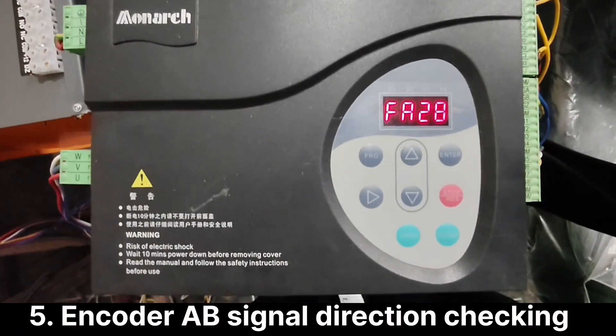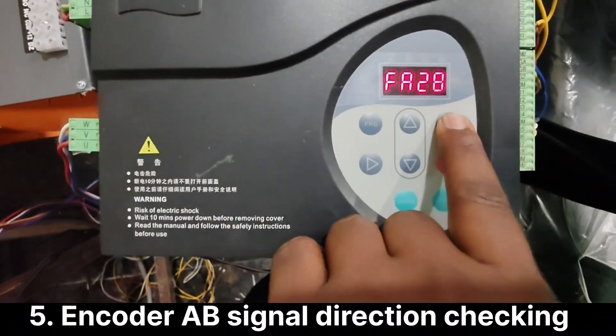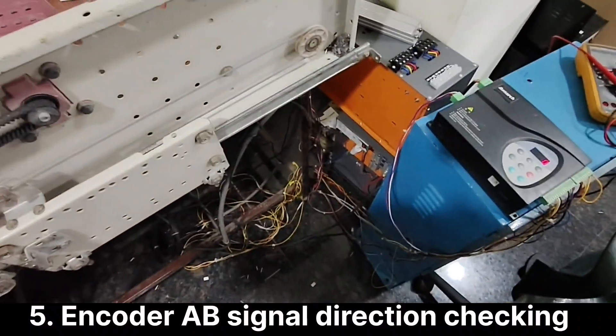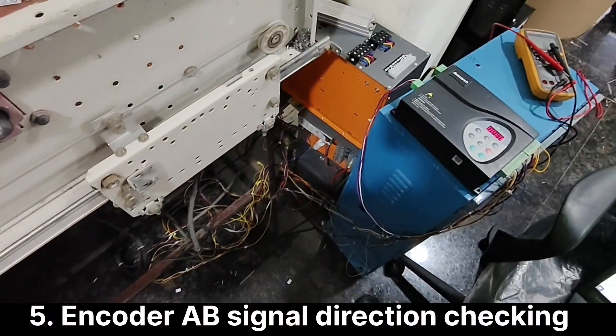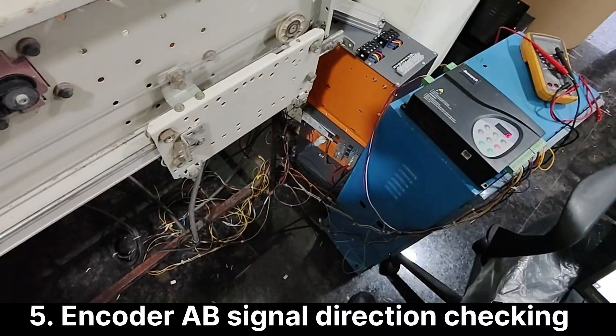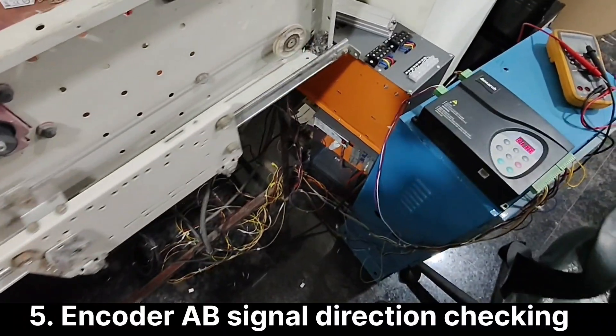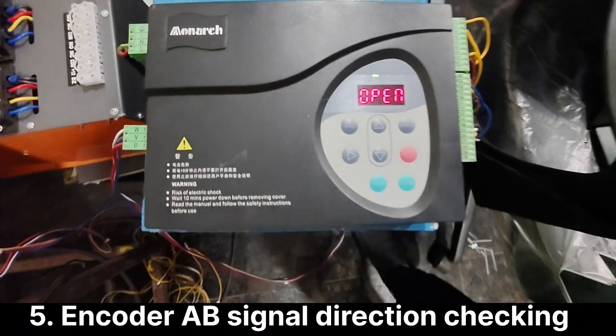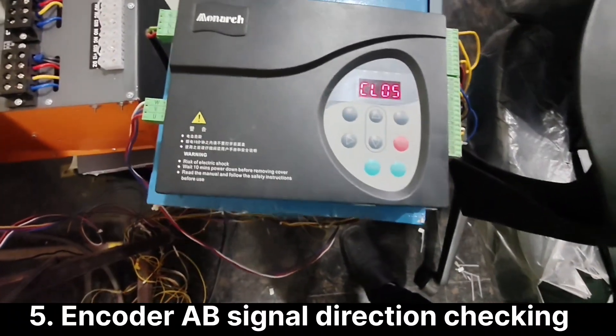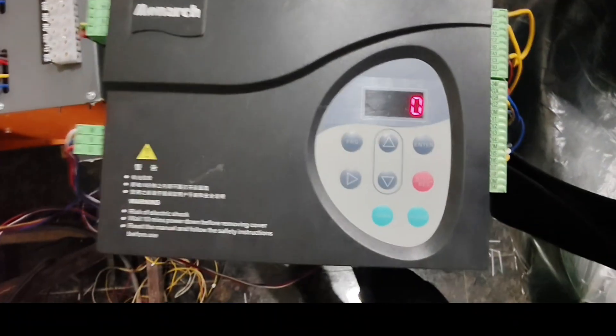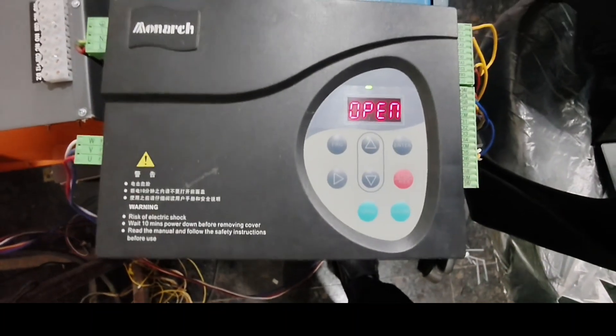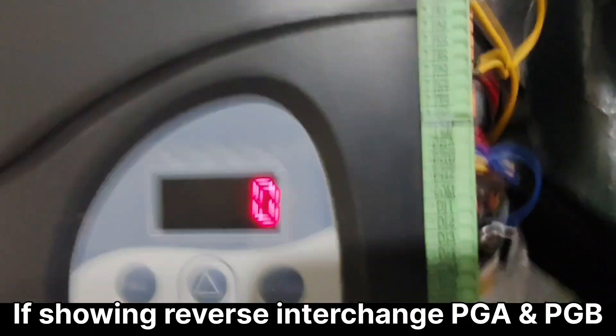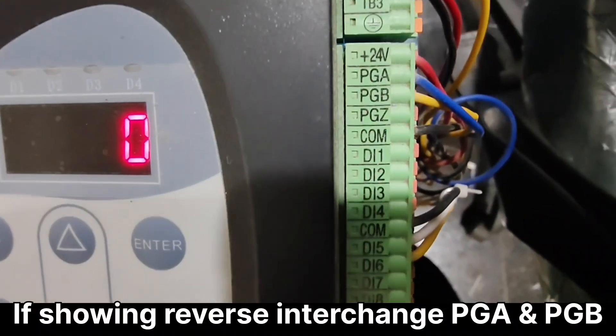For encoder direction FA28, when we open the door, display should show open. When we close the door, display should show close. If it's showing the opposite, then interchange the PGA and PGB signals.